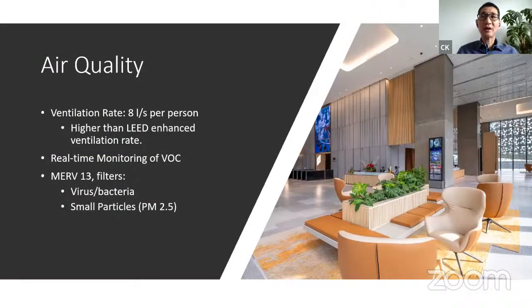Now, in terms of air quality, I talked about the enhanced ventilation; it's actually more than the LEED enhanced ventilation rate. It follows the European standard. Studies have shown that with a higher fresh air ventilation rate, occupant performance is higher. So we are using the European ventilation rate for office occupants. We have real-time monitoring of VOC. If VOC suddenly goes up, we can increase the fresh air or go to that floor to identify the source of the VOC and remove it. So there's an active monitoring system of VOC implemented. We also put in MERV13 air filters, which address viruses and bacteria, and also small particles, PM2.5.